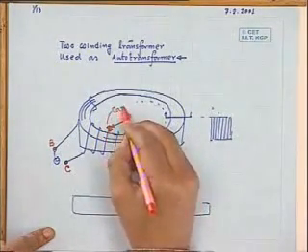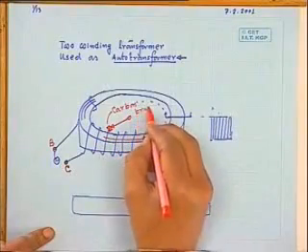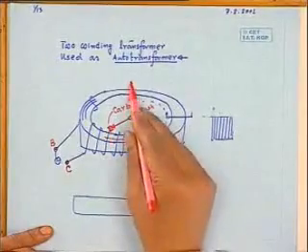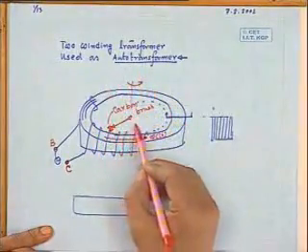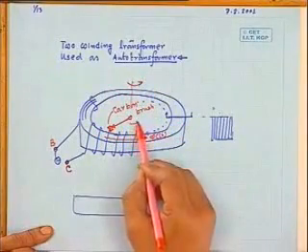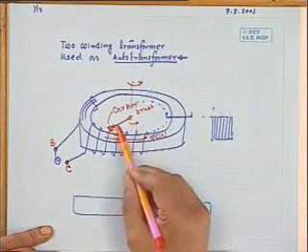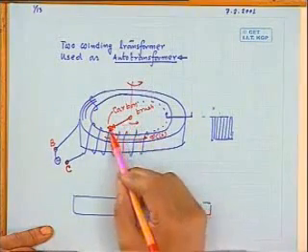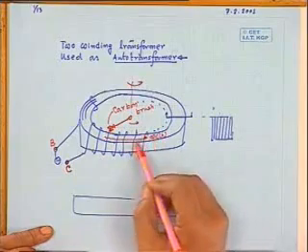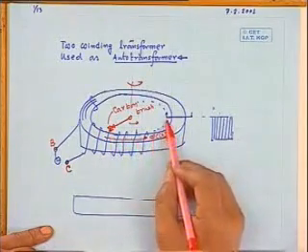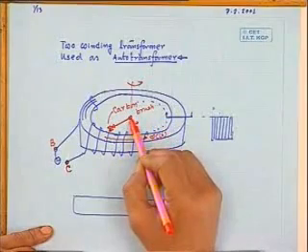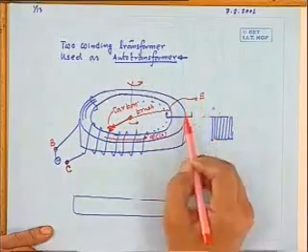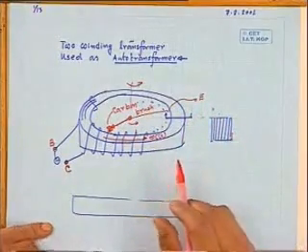This is the carbon brush, and this can be rotated externally. Suppose I move it like this, and through this handle goes a wire which is electrically connected to the carbon brush. As you move it, the carbon brush will touch different tappings, different turns, thereby changing the number of turns. And this wire is taken out and called E, the variable point, like the jockey of a rheostat.